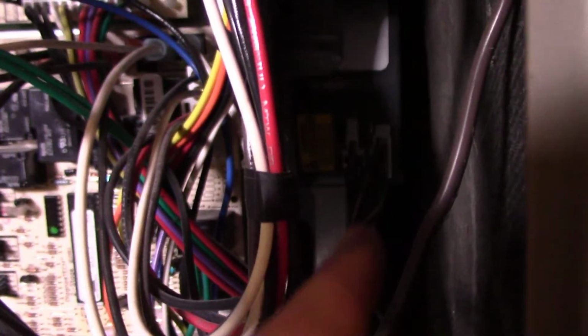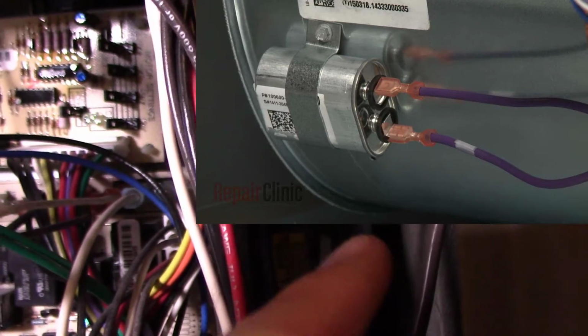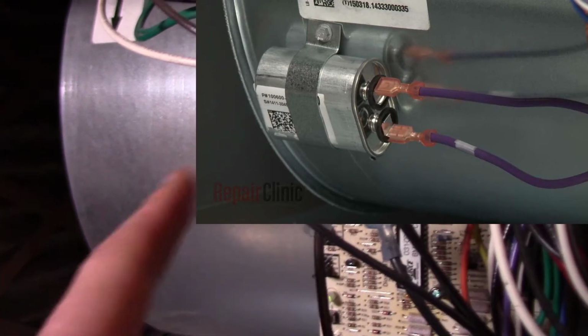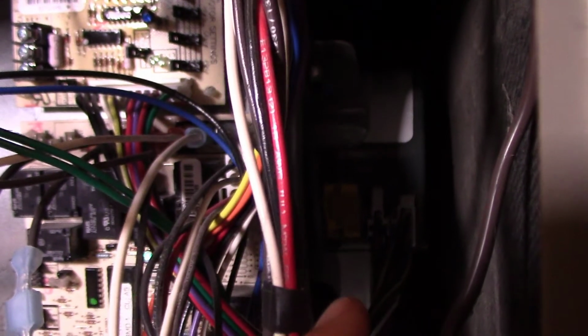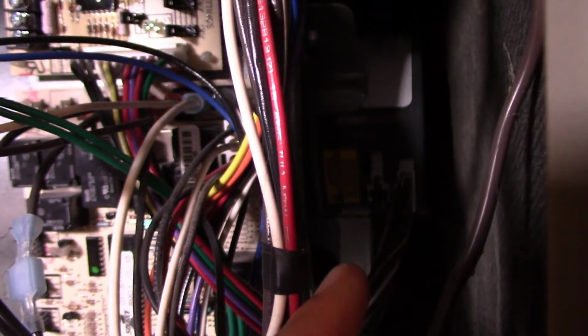I'm not seeing the run capacitor on mine. This might have the run capacitor built in inside of that motor assembly, but sometimes you'll have the capacitor running in between the wires of the motor and the board. There'll be some sort of capacitor, usually mounted on the tin somewhere around the motor. If you have one of those, that may be the first thing you want to replace because they're much cheaper than the actual motors themselves. Otherwise, you might have to replace the motor. That's it for the furnace troubleshooting.